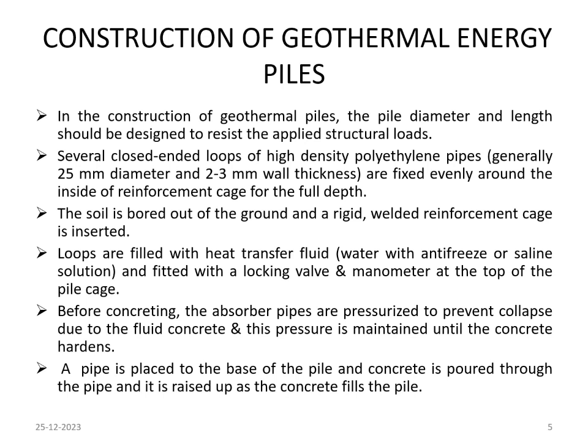These fluids are water with antifreeze or saline solution, fitted with a locking valve and manometer at the top of the pile cage. Before concreting, the absorber pipes are pressurized to prevent collapse due to the fluid concrete, and this pressure is maintained until the concrete hardens.